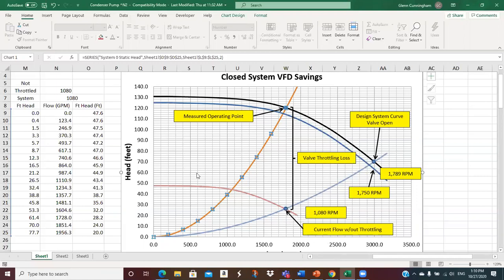Well, so what you do is, you estimate this. Well, this is just one more system curve. You've got your design operating point, what the pump's supposed to be capable of. You've got your zero static head. So you just fit another system curve, which is this one, plot it up, goes through there. Then this is kind of a cool trick. So now you plot another curve, and remember, I'm at 1080 on my speed.